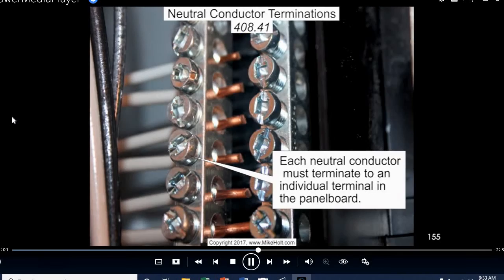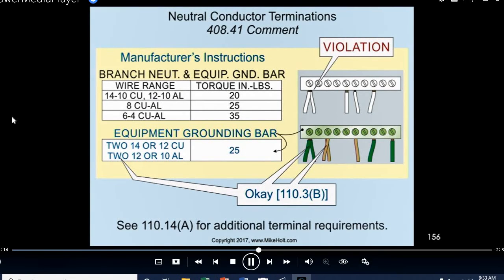Neutral conductor terminations. The neutral bar is to be used for the neutral conductor, and only one neutral conductor is permitted to be installed under a given terminal. You see this violation a lot. Here's an example where you have instructions, and these instructions tell you the torquing requirements.